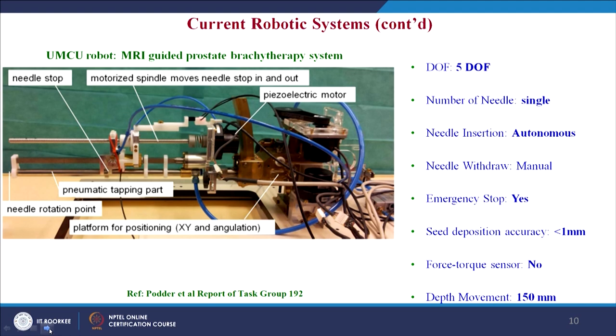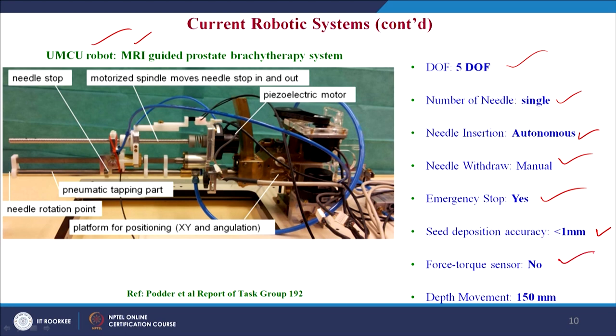Next is the robotic system developed by the research team at University Medical Center Utrecht in the Netherlands — an MRI-compatible robotic system for online MRI-guided prostate brachytherapy. This system has 5 degrees of freedom, single needle, autonomous needle insertion, and manual needle withdrawal. It is provided with an emergency stop, seed deposition accuracy less than 1 mm, no force-torque sensor, and a depth movement of 150 mm.